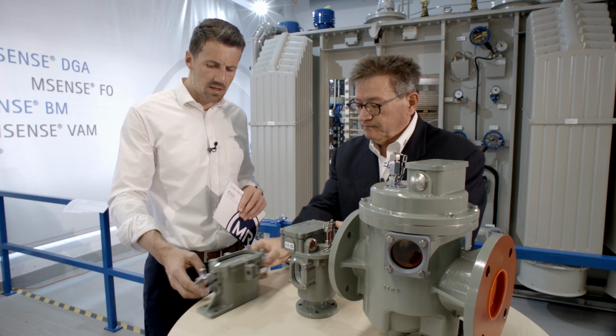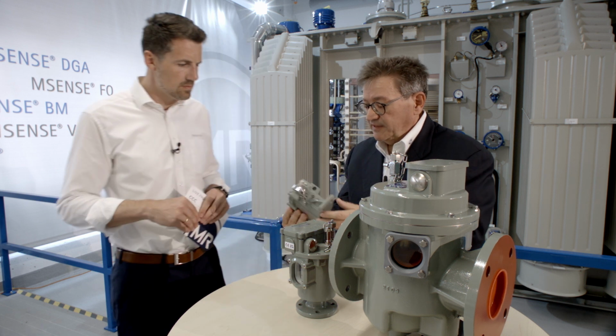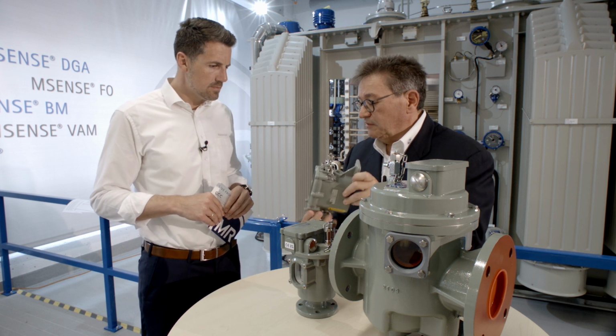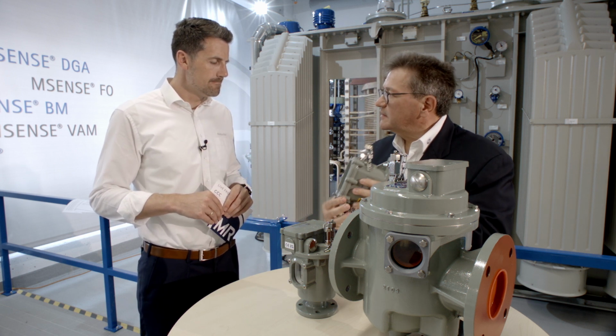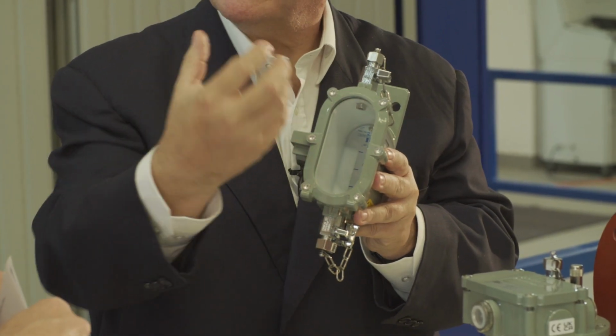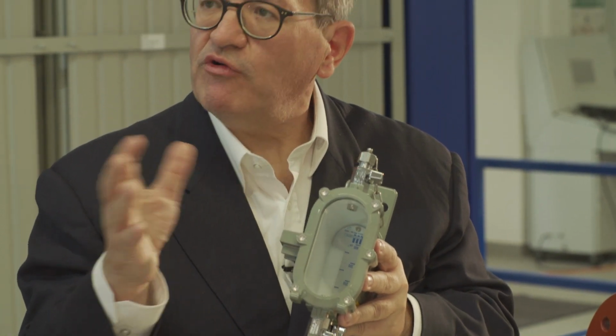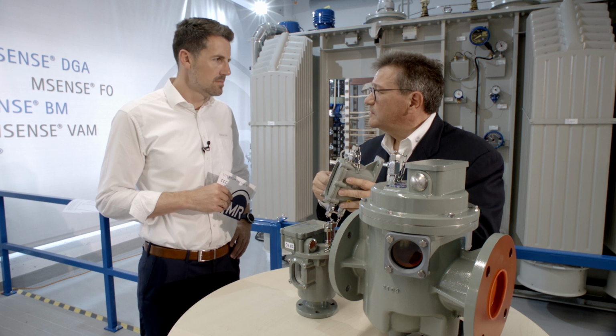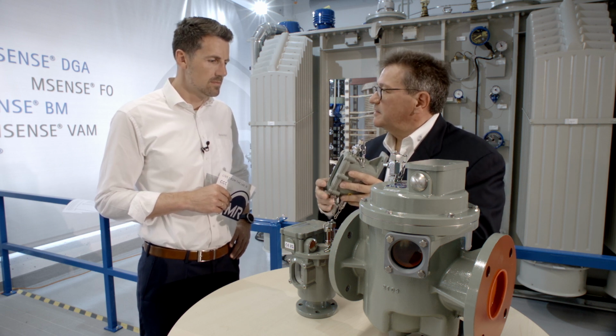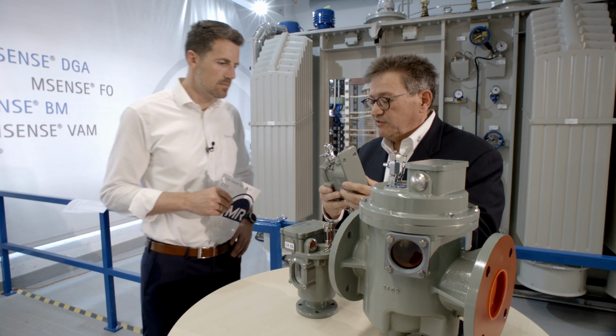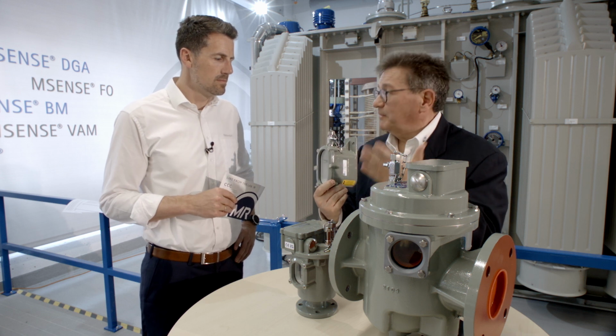Last but not least, the gas collecting device. What is the purpose here? Gas collecting device is a complementary device of the Buchholz Relay. We said that Buchholz is collecting gas, accumulating gas coming from the transformer just in case of small failures, small electrical arcs. This gas, once accumulated by the Buchholz Relay, once you have an alarm, you need to drain this gas to go to a chemical laboratory and to perform a chemical analysis. So this device is normally mounted at man level on power transformers. And it helps the service people to drain the gas from the Buchholz without the need to jump on the top of the transformer.